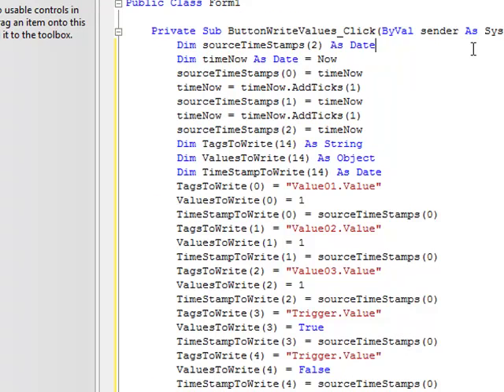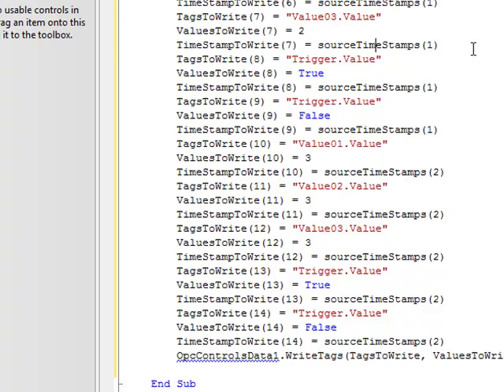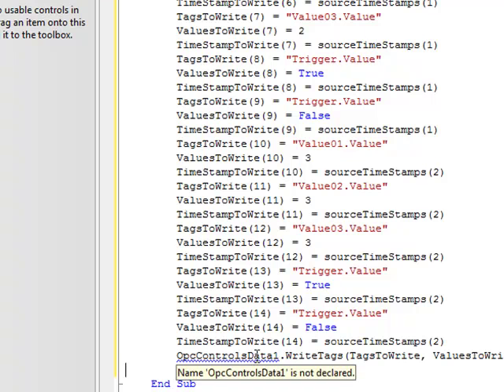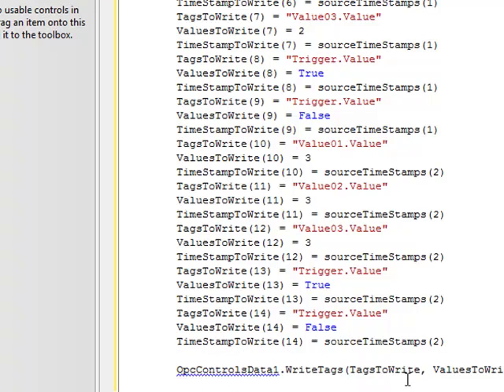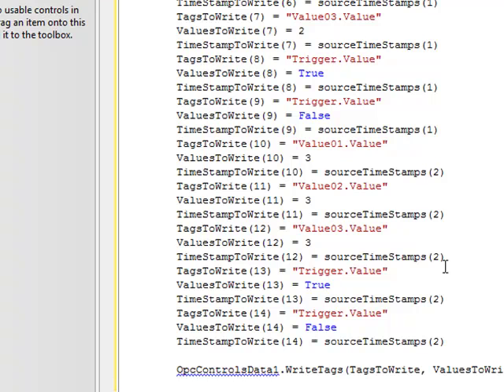In the code we have copied from the training guide, we are setting up some arrays of tags, values, and time stamps that we want to write to the real-time service. The last piece of the code is we need an OPC controls data component in order to write the values to. That is the one simple method used to write to a real-time database. And remember that we are going to log based upon event for every time the trigger tag transitions from false to true. So in this code example, we are actually transitioning the trigger multiple times in the one write method. So this way you can write thousands of values per second and log them all.